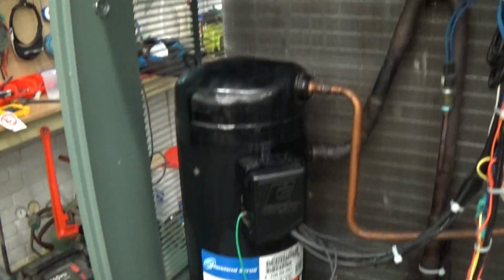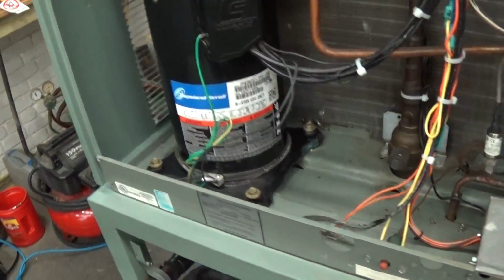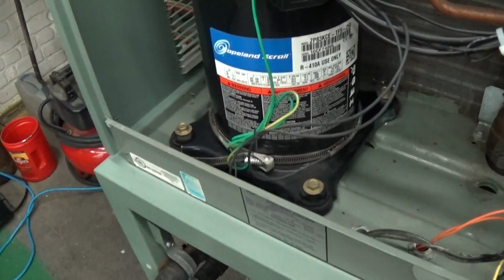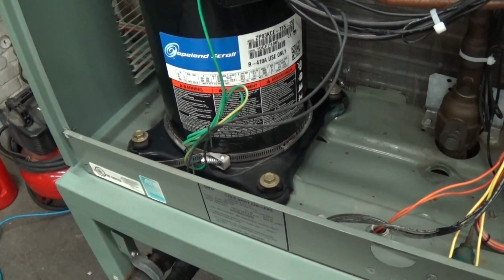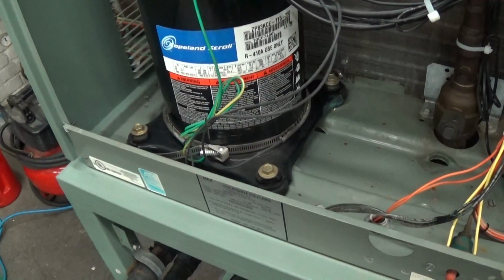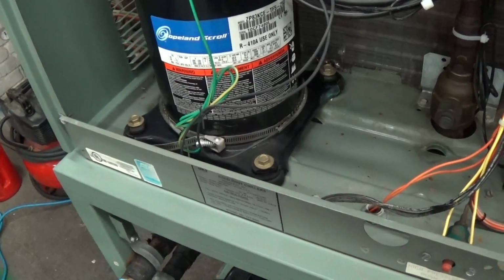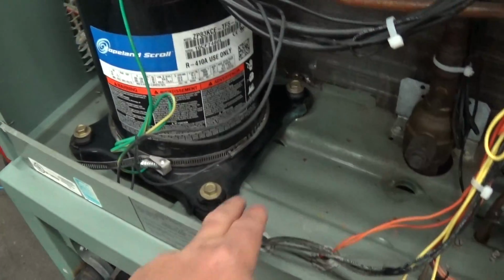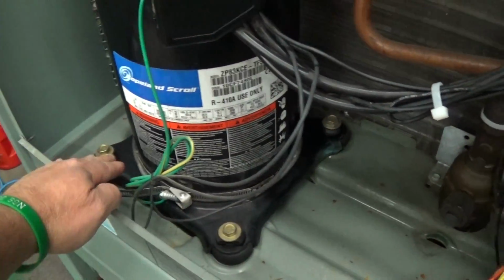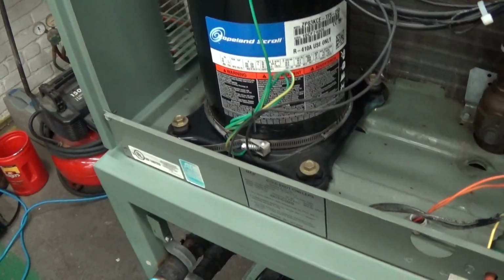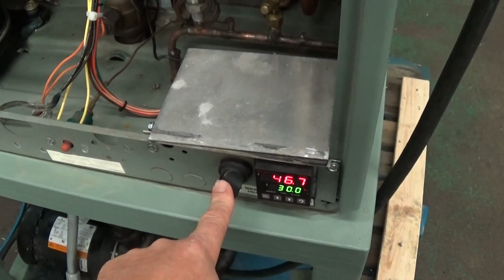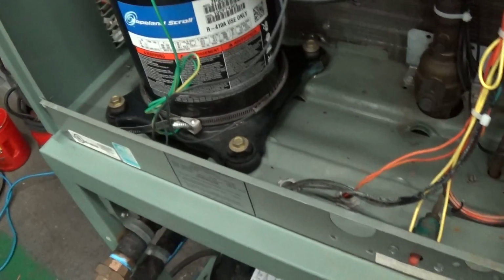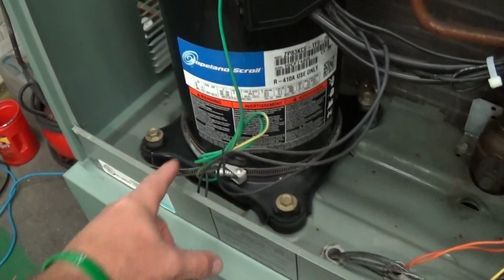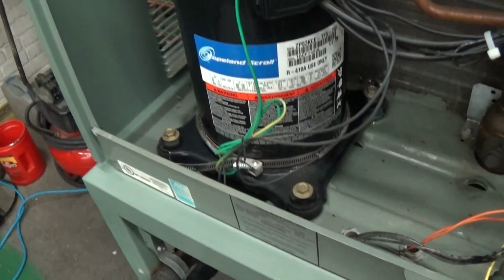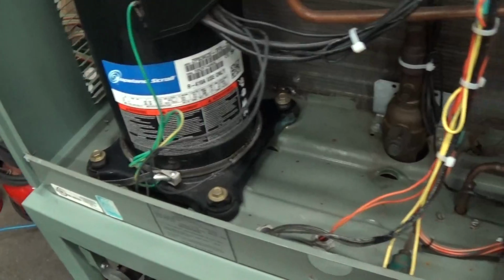This is your 7.5 horsepower Copeland compressor. After you do get initial power to the unit, it's a good idea to leave it under power, or before you turn it on, wait about an hour. This is a crankcase heater. This is always on. As long as there's power to the unit, even if you have the off button on, as long as there's power coming live into the chiller, this heater stays on all the time. That keeps the refrigerant from getting too cold in a cold startup condition.